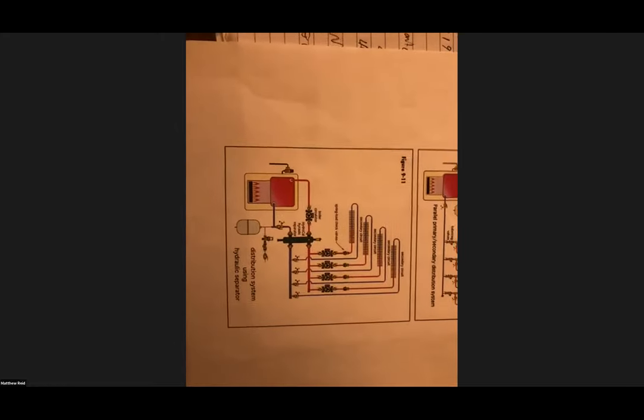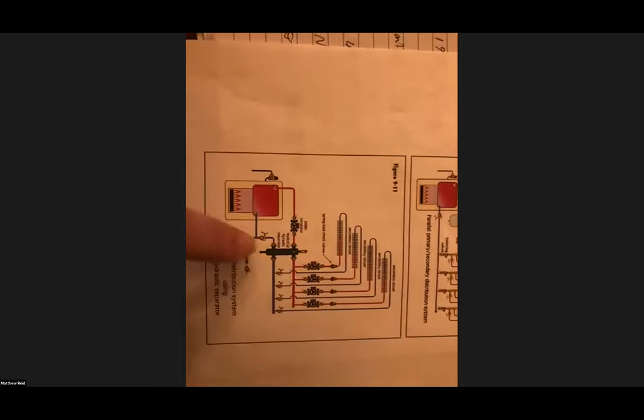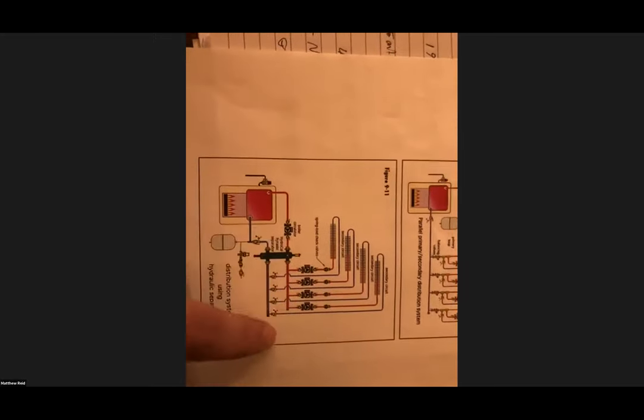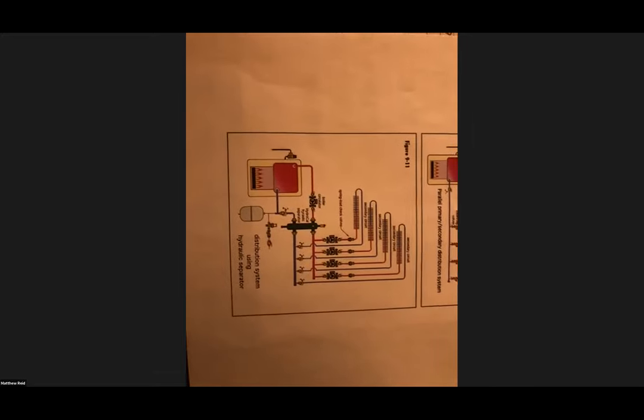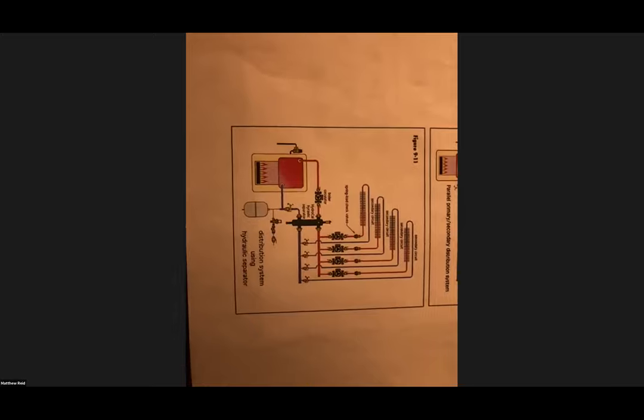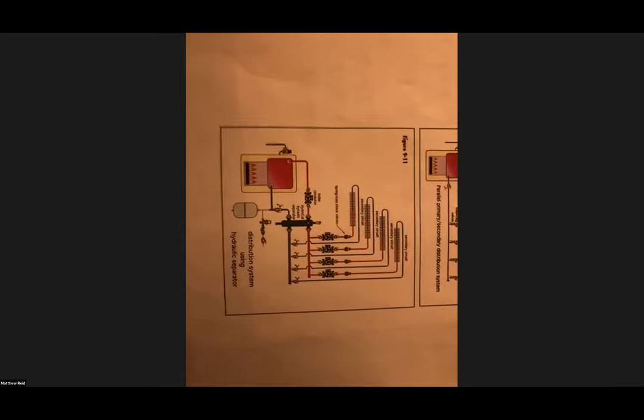Now this is a much more common system nowadays. So we have our boiler coming out, creating its primary loop to its hydro separator, our branch headers with pumps. Now, Canada is a pumping market. We zone with pumps. We're not huge on zone valves up here for whatever reason. Again, I'm not here to judge. I'm only here to talk.